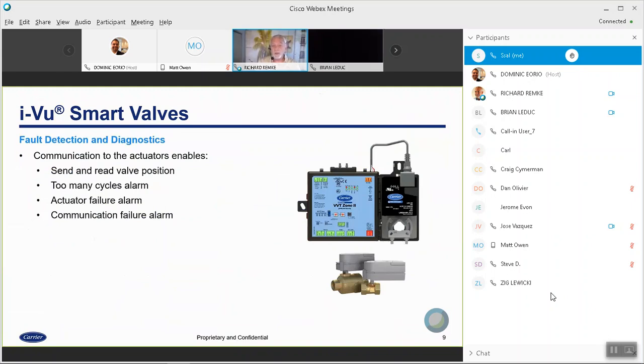One of the things that this really enables, and we put this into the library now so that you can download it, is fault detection and diagnostics. With the communication to the actuators, you get the ability to send and receive valve position. You can get too many cycle alarms, actuator failure alarms, communication failure alarms. All those alarms are already built into the library. They become enabled once you get the valves installed.